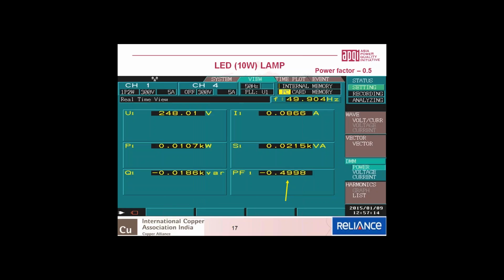The power factor should be a good power factor for a lamp. If not 1, it should be at least greater than 0.9. But this is an extremely poor power factor, and therefore there may have to be some regulations when you are introducing LEDs in a very big way, about harmonic distortion limits and the power factor of operation.